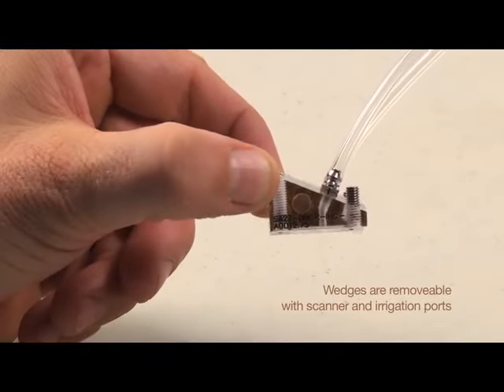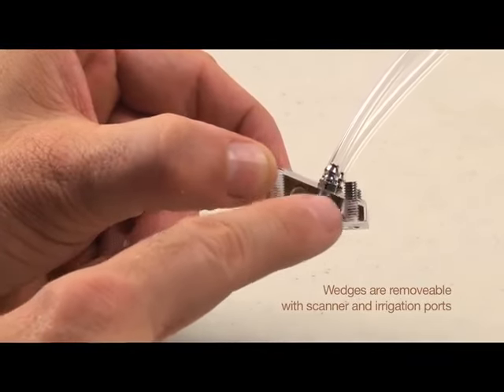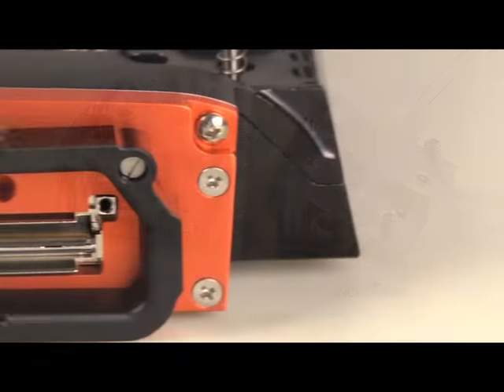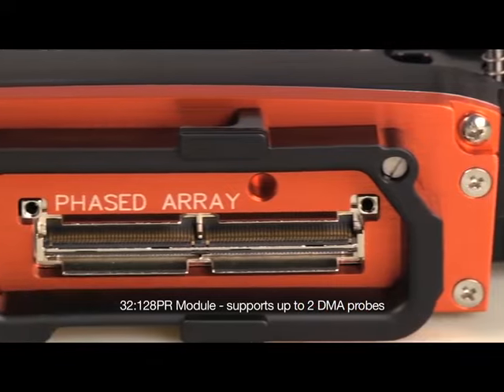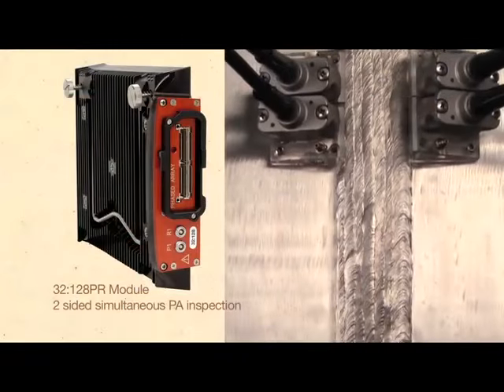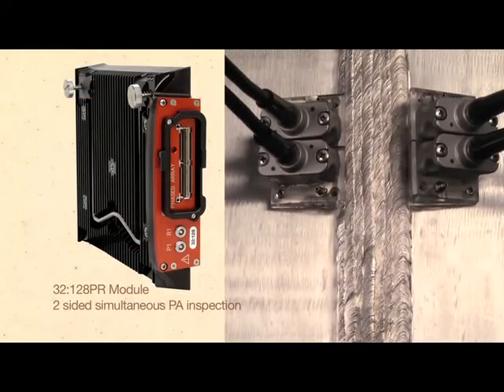DMA probe wedges are removable, come with scanner and irrigation ports, and are designed for either volumetric or shallow surface inspection similar to conventional UT-TRL creeping wave probes. The 32128 PR module supports up to two DMA probes for two-sided simultaneous phased array inspection.